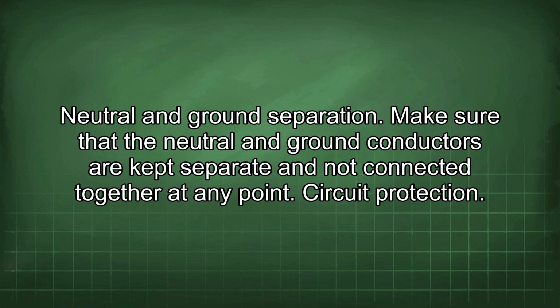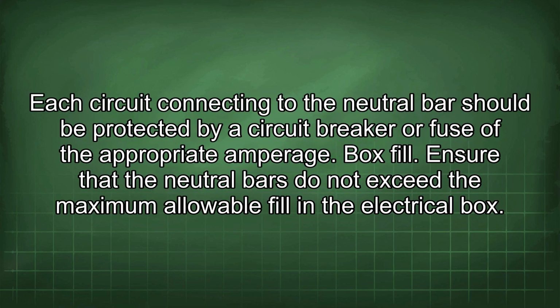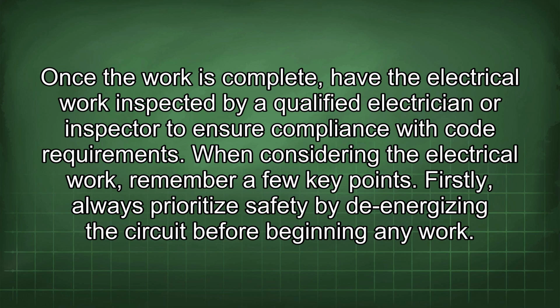panel. Neutral and ground separation: make sure that the neutral and ground conductors are kept separate and not connected together at any point. Circuit protection: each circuit connecting to the neutral bar should be protected by a circuit breaker or fuse of the appropriate amperage. Box fill: ensure that the neutral bars do not exceed the maximum allowable fill in the electrical box. Once the work is complete, have the electrical work inspected by a qualified electrician or inspector to ensure compliance with code requirements. When considering the electrical work, remember a few key points.